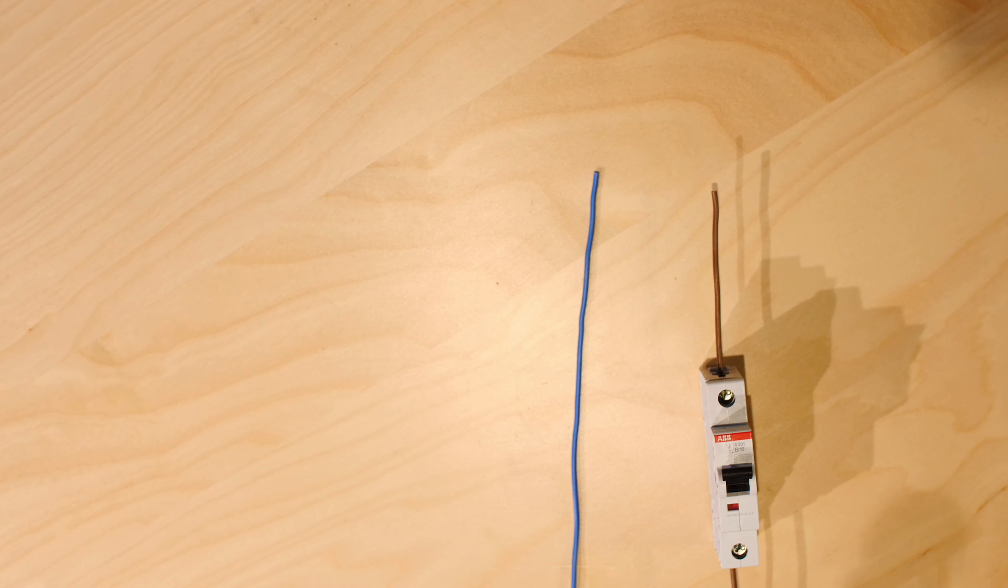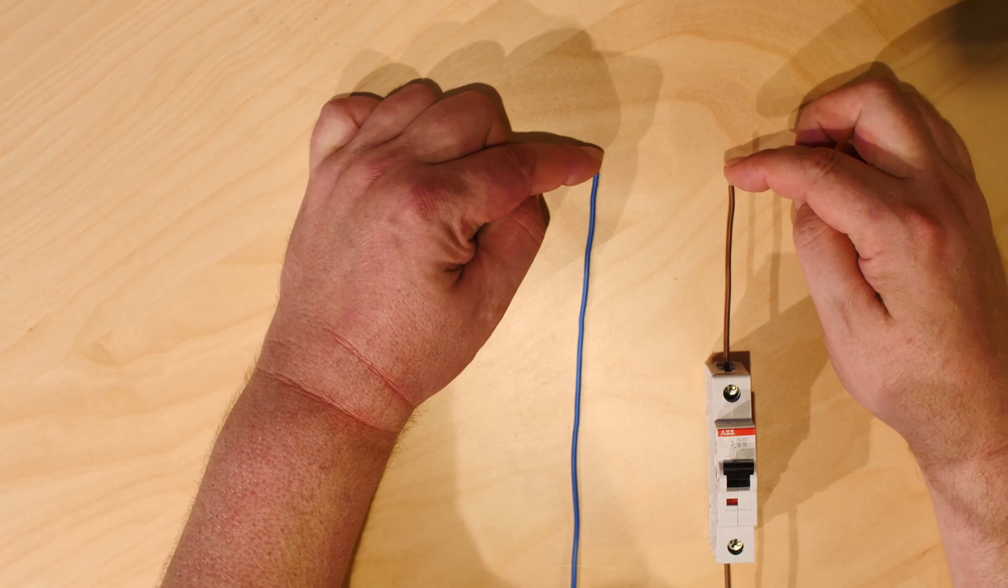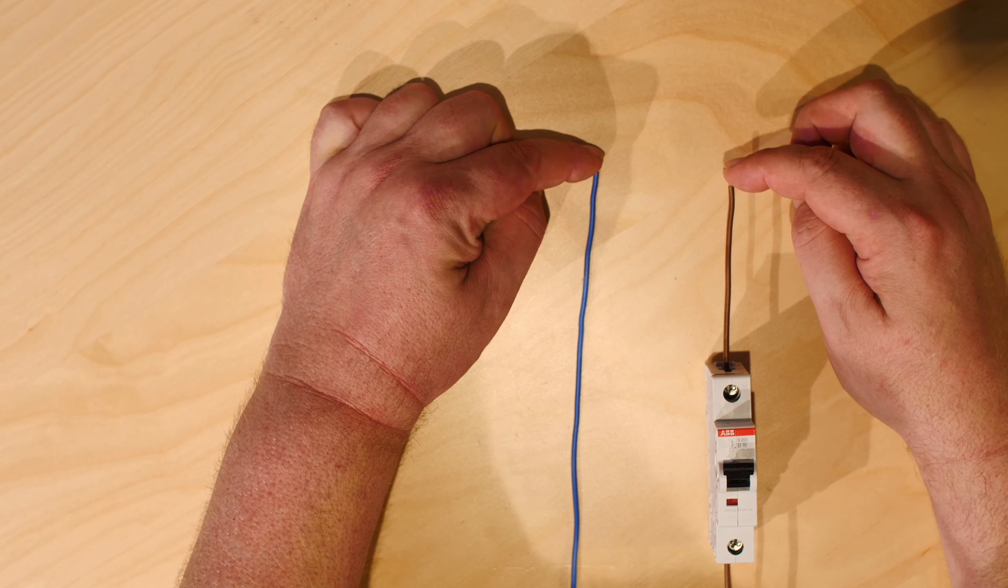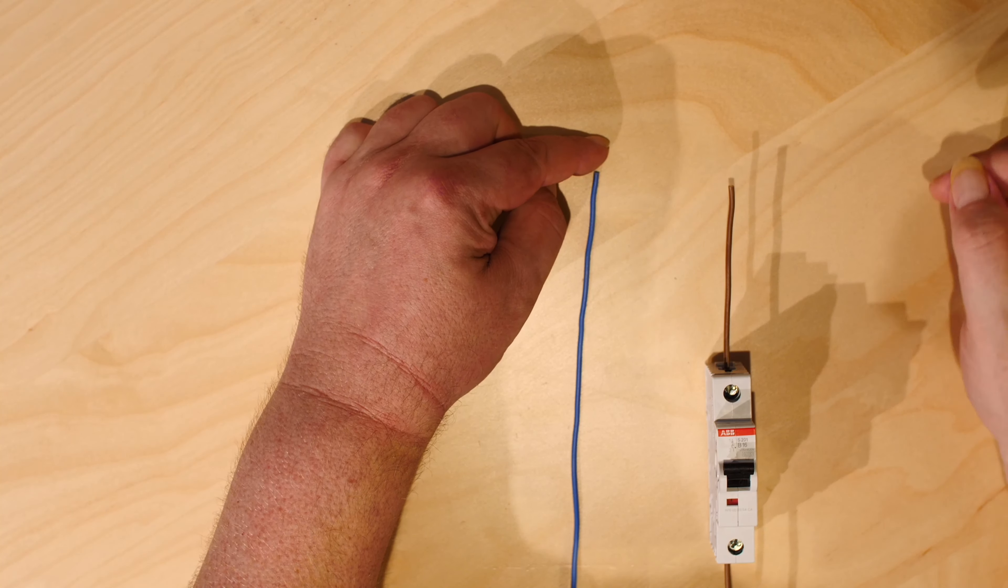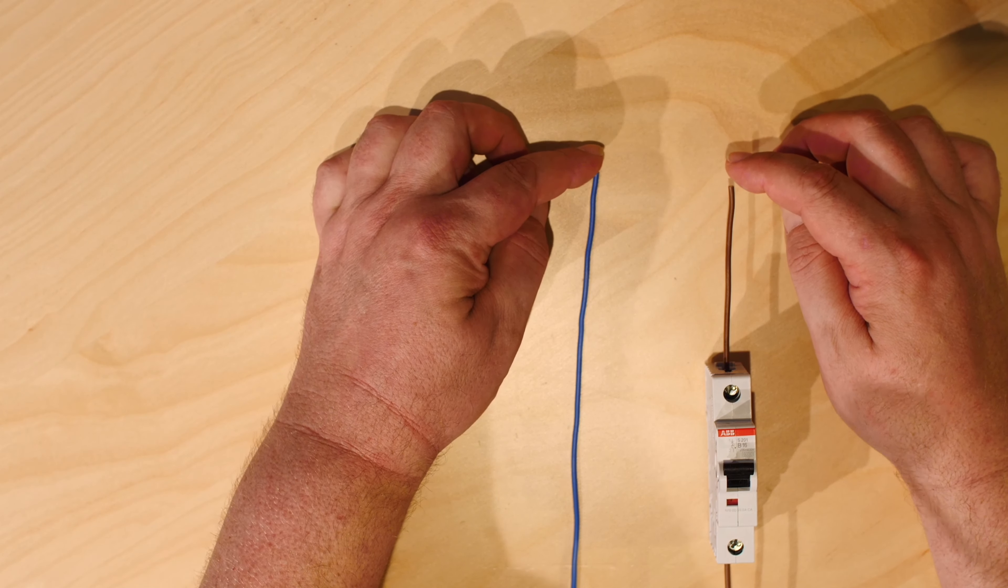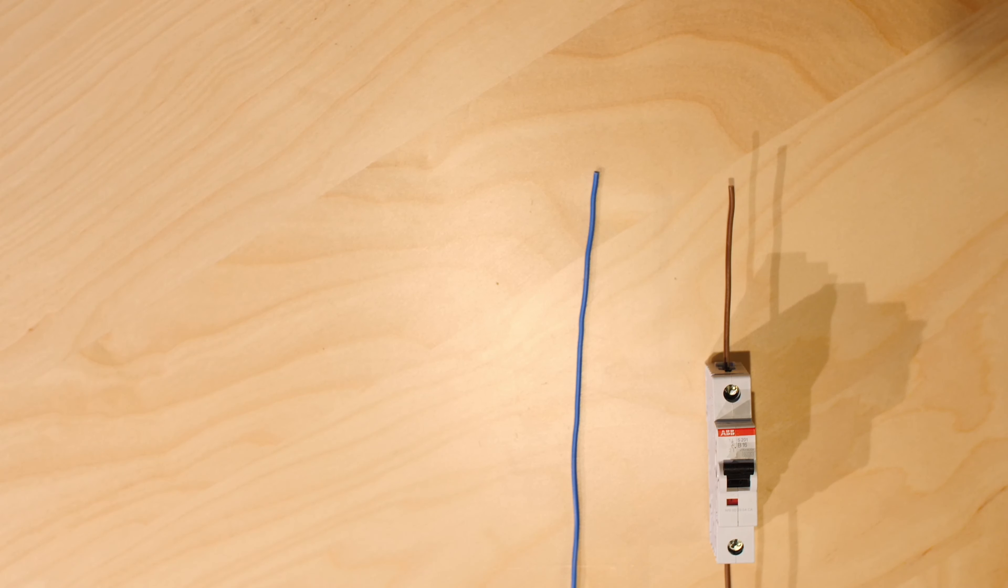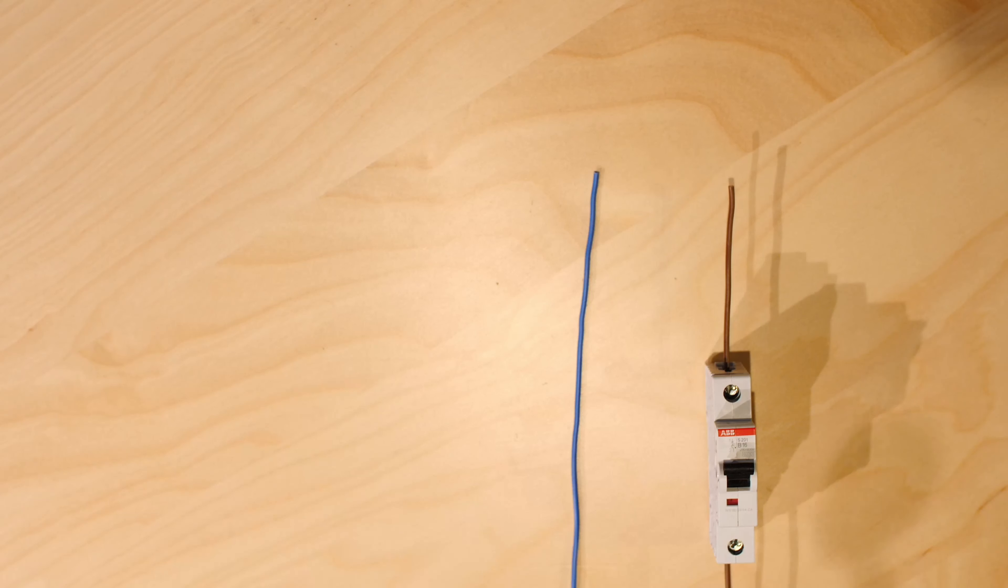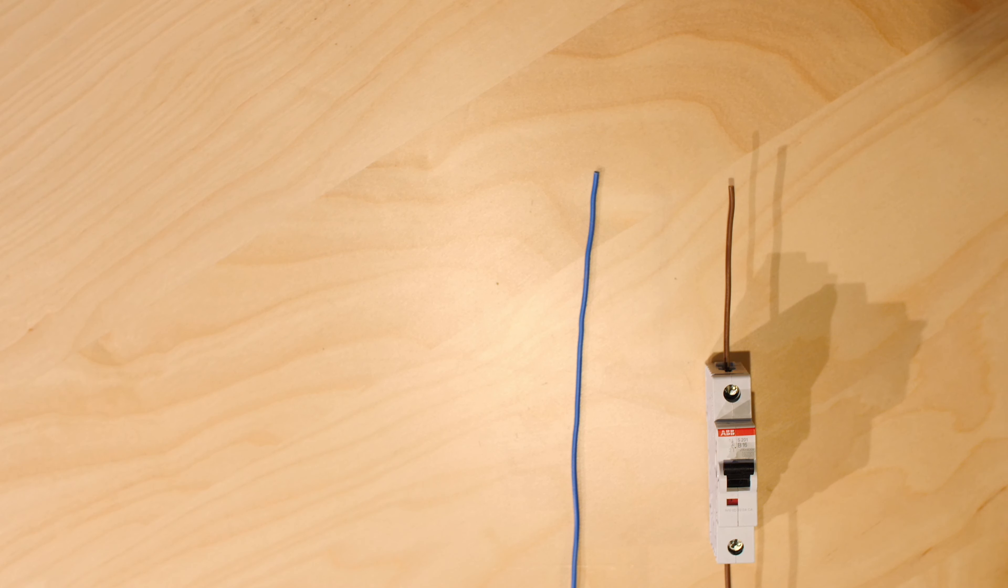Neither this kind of fuse, if you have this in your house, or if you have this circuit breaker in your house, they will not protect you from anything happening to you if you get an electric shock. For example, if I touch these both here with my fingers, the current will run through my body and through the other finger and from there back to the plant. And my body is not like metal, it's not a perfect conductor, so I have a body resistance. For example, right now it's pretty hot here, my skin is a little bit kind of moist, wet, so my body resistance may be 1000 ohm or something like that. So there will be quite a bit of current running through my body, but not enough to switch off the circuit breaker. So there we have a problem.